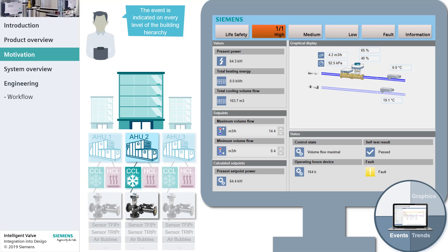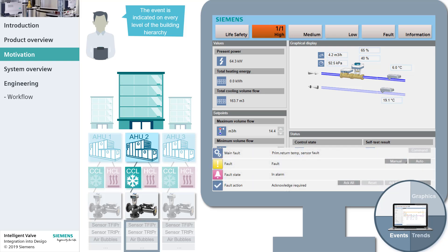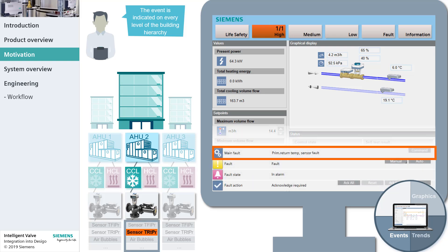The error description tells Mike clearly that there is a problem with the primary return temperature sensor connected to the intelligent valve. Mike grabs his toolbox, travels to the site, and fixes the broken sensor connection.